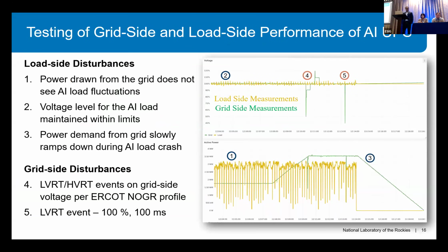So this is my last slide, where I want to talk about testing the grid side and load side performance of this AI UPS simultaneously. At the top are the voltages, and at the bottom is the active power. The orange measurements are on the load side, and the green ones are on the grid side.